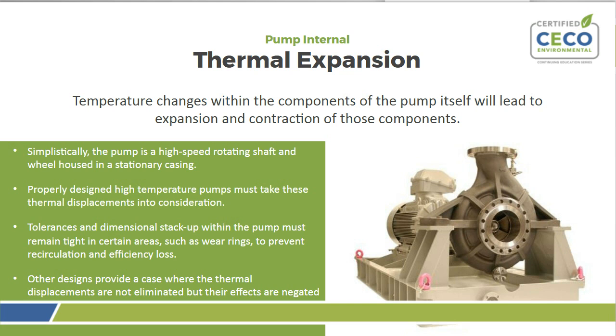So simplistically, the pump is a high-speed rotating shaft and a wheel housed in a stationary casing. Of course, the high-speed rotating components cannot touch the stationary components. The pump will not operate very well. That would be problematic. Properly designed high-temperature pumps need to take these thermal displacements into consideration. The tolerance and dimensional stack up within the pump must remain tight in certain areas, such as wear rings, to prevent recirculation and efficiency loss within the pumps.